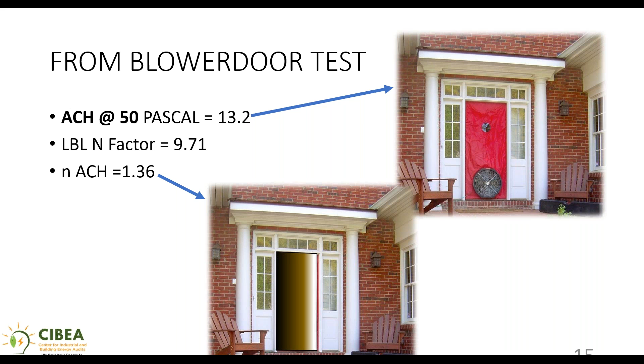A typical building on common normal days is in use with a certain air pressure, and because of that there is a level of leakage in the building. With the blower door, because we have hugely pressurized or depressurized the building, we get very high ACH values, but we can convert them into normal day ACH as well. So without pressurization, the leakage going on in the building will be at a level of 1.36 for an ACH 50 of 13.2. We should be careful about not comparing this number with the ASTM lower limits, because the ASTM limit is on ACH 50, which is the blower door test reading, not the converted one.